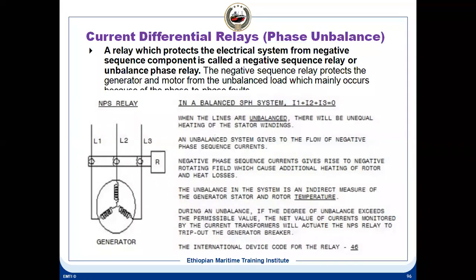In the case of a generator, that means there is an indirect measure of the generator stator and rotor temperature. It can also cause unbalance in the system. If the unbalance exceeds the permissible values, the net value of the currents monitored by the current transformer will actuate the unbalanced NPS relay, the negative phase sequence relay, to trip the generator breaker. In motors also, unbalanced relays can be used.